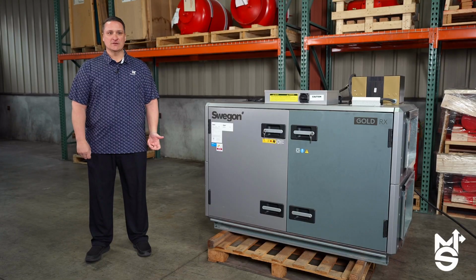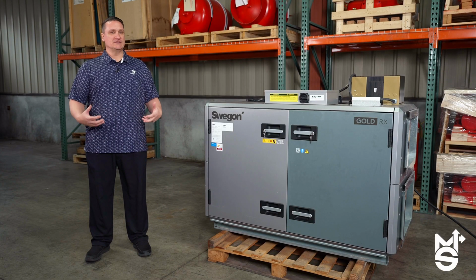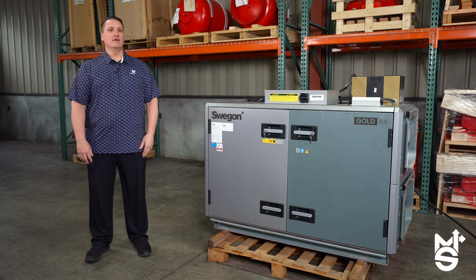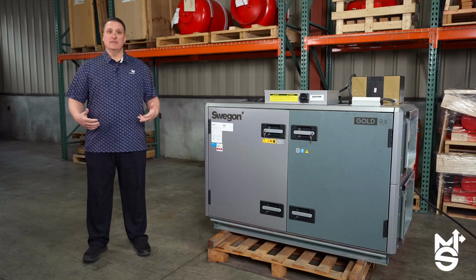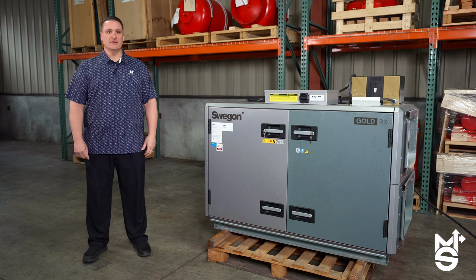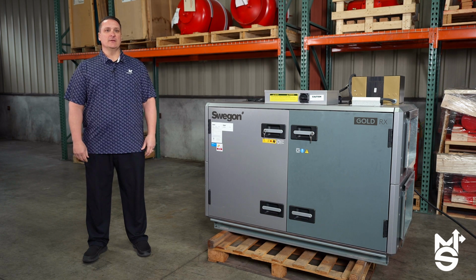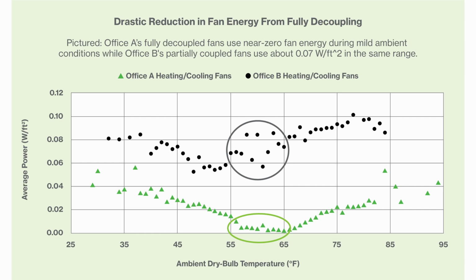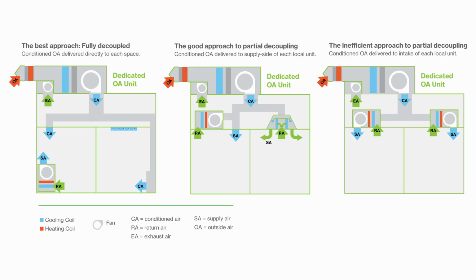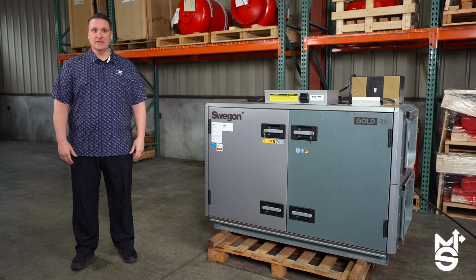Each zone is then heated or cooled depending on its unique load in the zone by the terminal unit located in that zone. This terminal unit recirculates the air in each zone and is decoupled or separate from the outside ventilation air of the ERV. Examples of terminal units can be various types of fan coil units or active chill beams. This decoupled system greatly increases HVAC efficiency as well by right-sizing the zone equipment to each zone load. Keeping each zone independent increases building indoor air quality by not recirculating air. Dedicated outside air is delivered to each zone, then returned to the ERV for energy recovery and exhaust outside the building. What types of projects and owners are benefiting from VHE DOAS systems?